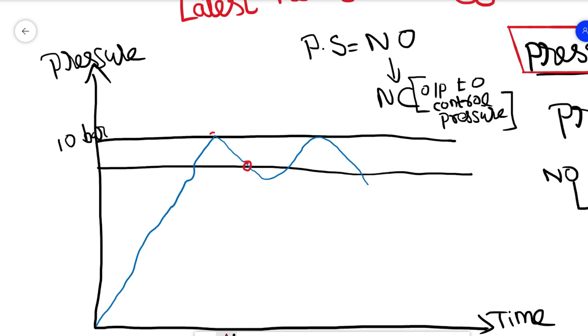And then the pressure switch contact changes over to its normal condition, that is normally open contact. You can see over here, this is the actuation pressure and this is the reset pressure for this pressure switch. And it's very clear that from this point to this point, there is no actuation of the pressure switch.